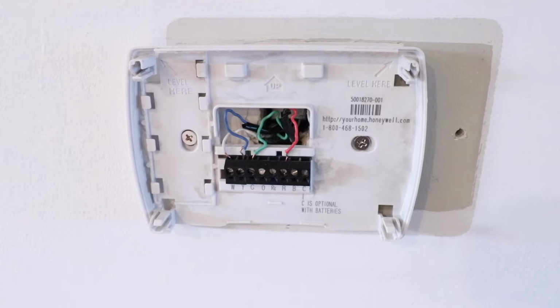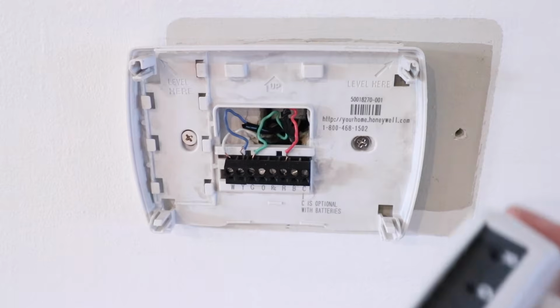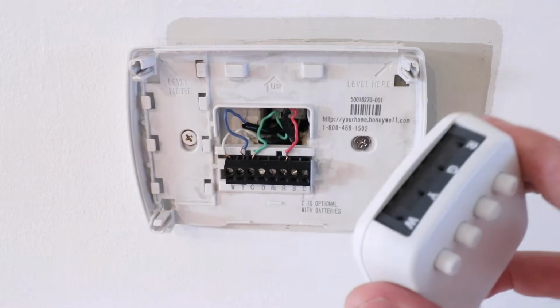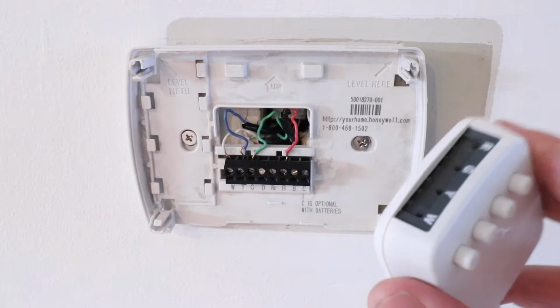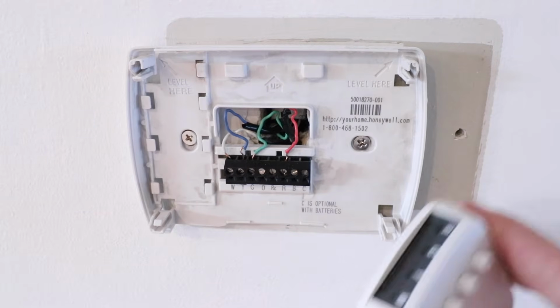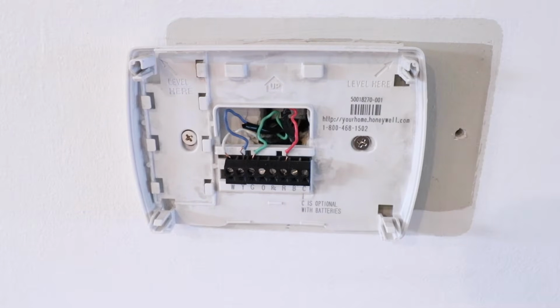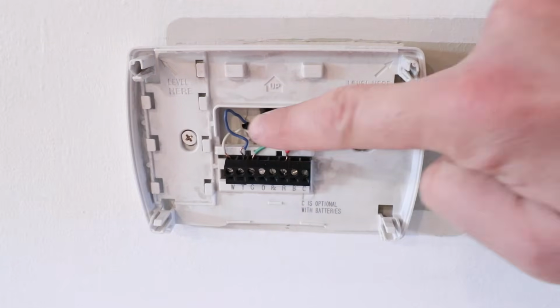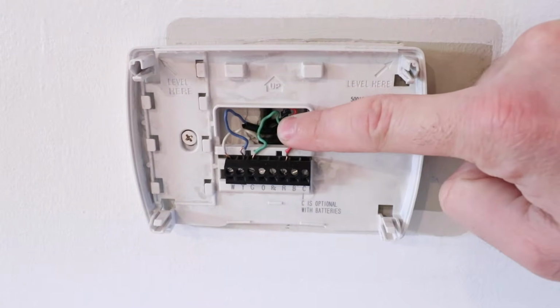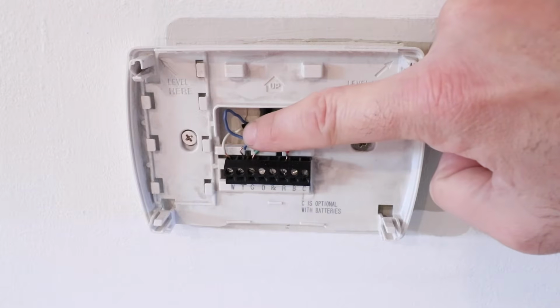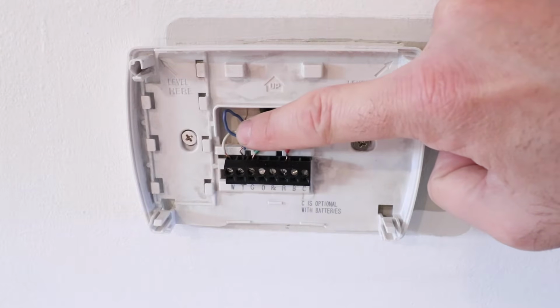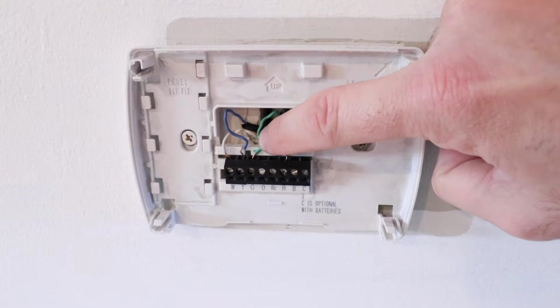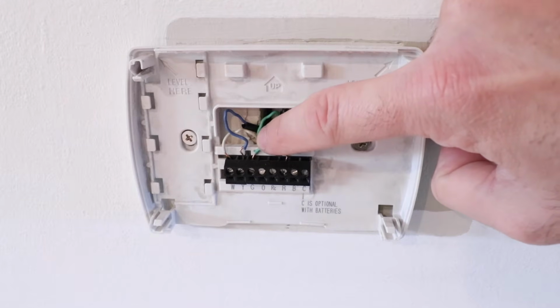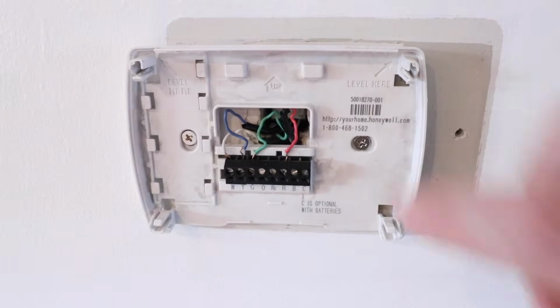So we're going to need to use this power extender kit that comes with the Ecobee thermostat, and that means our wiring is going to be a little different. We're going to have to go back to the HVAC system and install this power extender kit with the wiring there. Another change is that when we come back here, our wire labels will be a bit different: our Y wire will be labeled for the PEK terminal, and our G wire will be labeled C for the common wire when we put on the new Ecobee thermostat base plate.